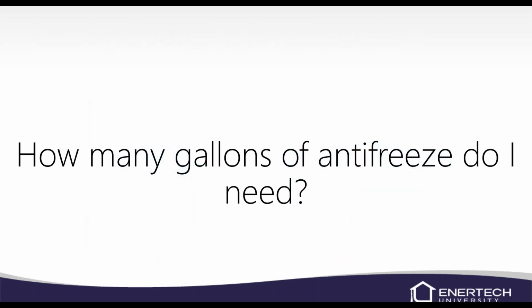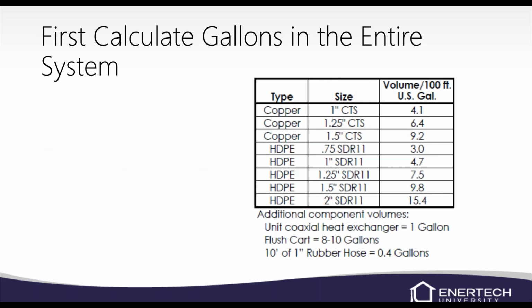You need to figure out how many gallons of antifreeze are in the system. In every single manual, we will give you this chart. It'll tell you if you've got copper or PE pipe, how many gallons are per 100 feet. And that's per 100 feet, not 1 foot. It'll also list right below that chart how much is in the heat exchanger, how much is in the flush cart, and how much is in the hose kit. You're like, well, the flush cart's not going to stay in the system, and you are right about that, but it is in the system when we add the antifreeze. And we will lose that fluid, but we have to account for it. So you're going to be wasting a little bit of antifreeze, but it's really not that much, so don't really worry about it too much.